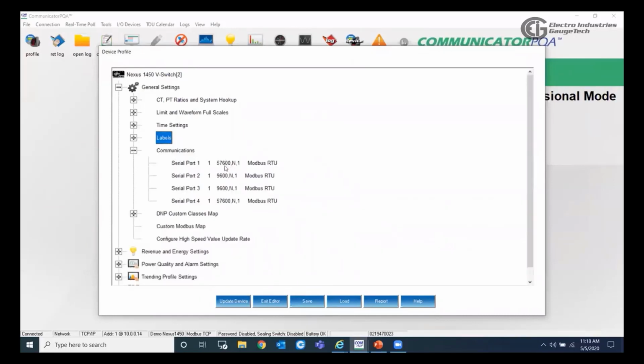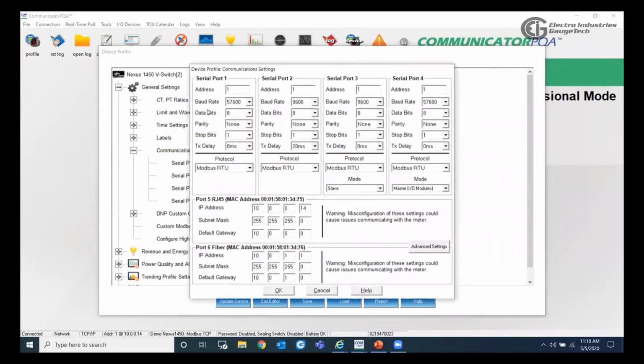Under the communications, it's one window for all of that. We can double click, and from here we can set the communication port settings. You can see the serial ports 1, 2, 3, and 4, and each can have a different address, different baud rates, and all the other settings, and the protocol also. Because port 3 and port 4 can be used to connect with input-output modules, we have this option here to choose between a master input-output module or a slave. If it's slave, it can be used to connect with the display or just to connect with the meter.